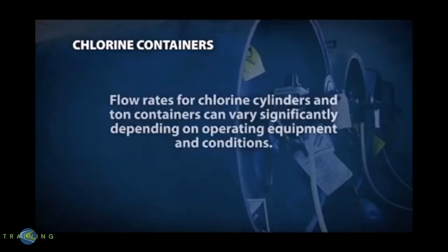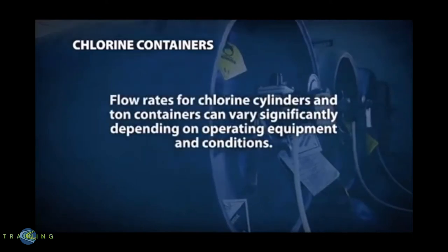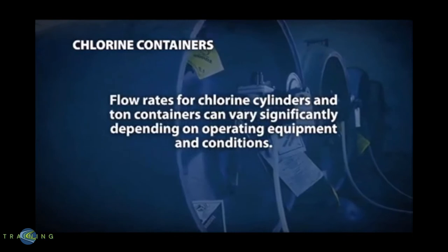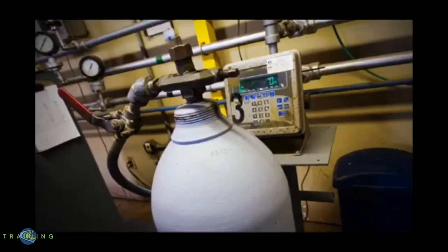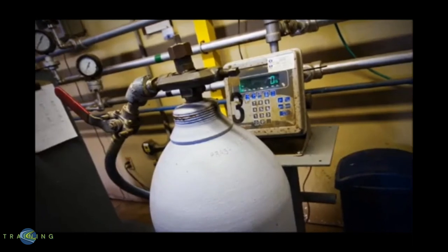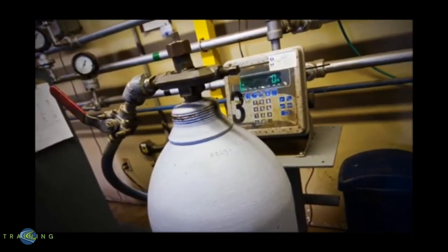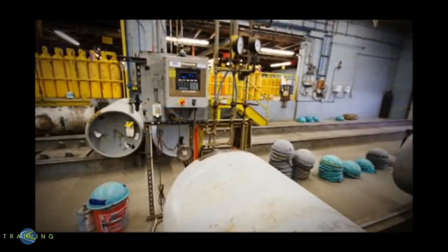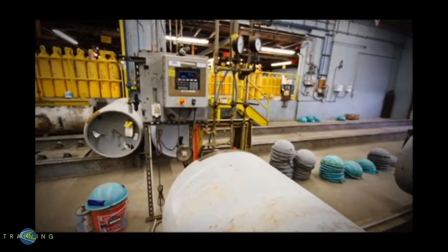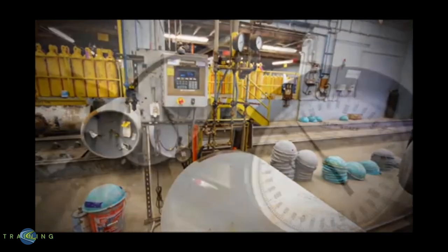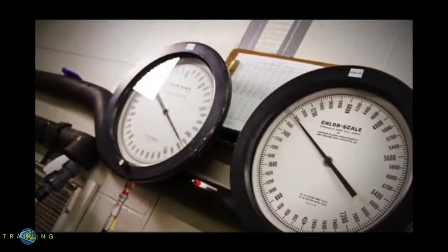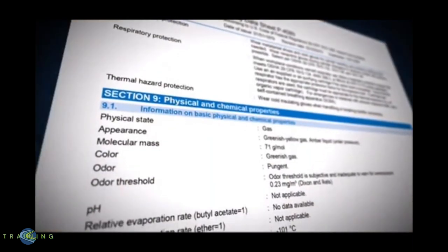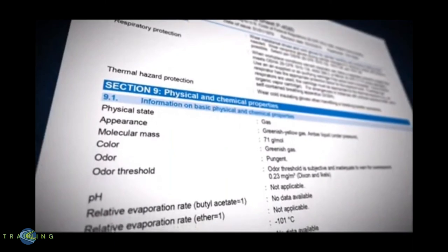Flow rates for chlorine cylinders and ton containers can vary significantly depending on operating equipment and conditions. The only way to make certain a container is empty of liquid chlorine is to weigh it on a scale. Chlorine vapors will remain in the container even when liquid is gone. To ensure scale accuracy, follow the manufacturer's recommendations regarding calibration. More information on chlorine's physical and chemical properties can be found in Section 9 of the Safety Data Sheet.